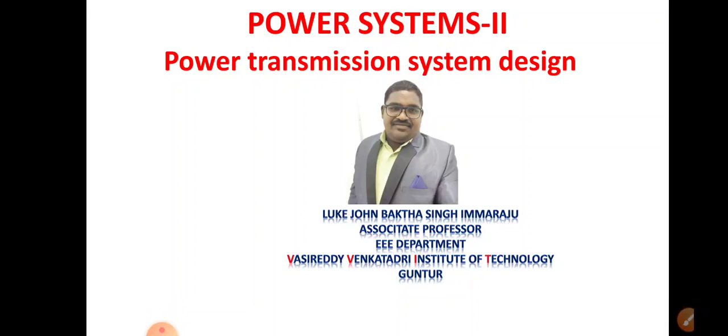The first one is, what are the advantages and disadvantages of Corona? Just tell me. We know the disadvantages very well. There is a definite loss of power, and there is a non-sinusoidal voltage drop due to non-sinusoidal corona current, and owing to the formation of corona, ozone gas is produced, which chemically reacts with the conductor and causes corrosion. These are the disadvantages of corona.